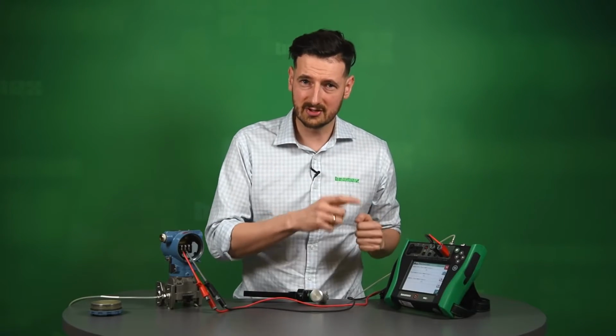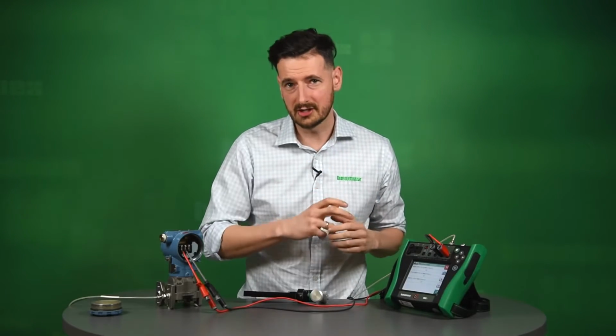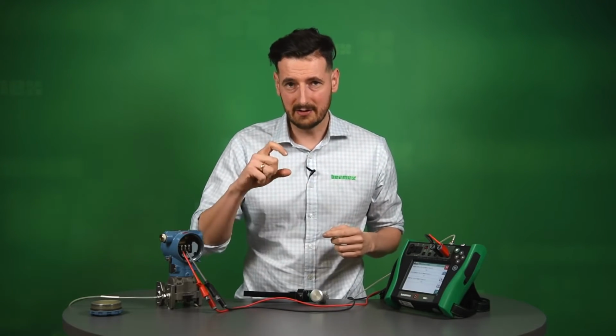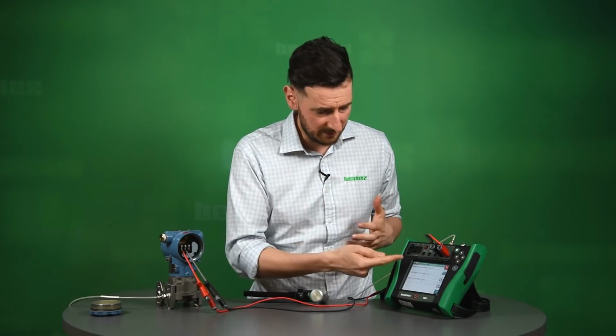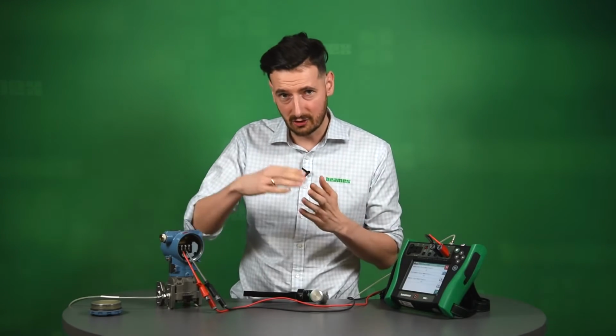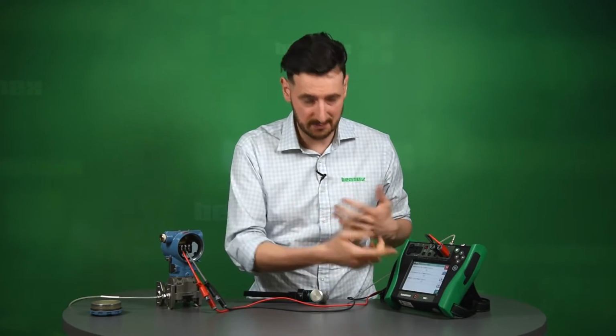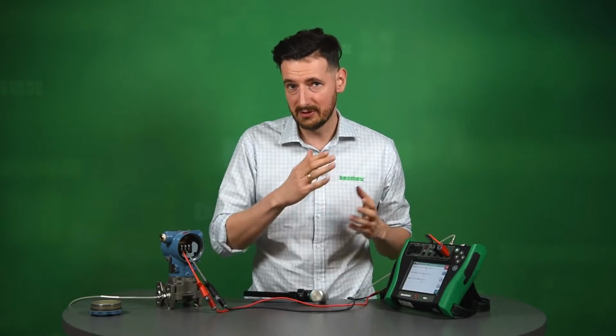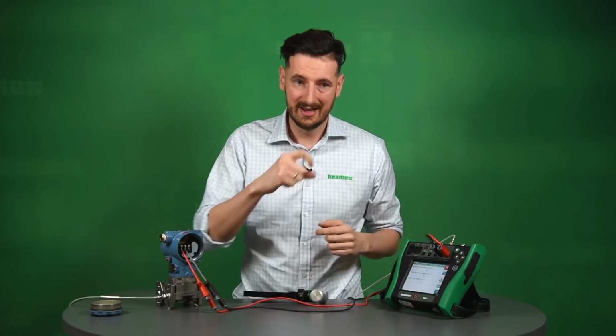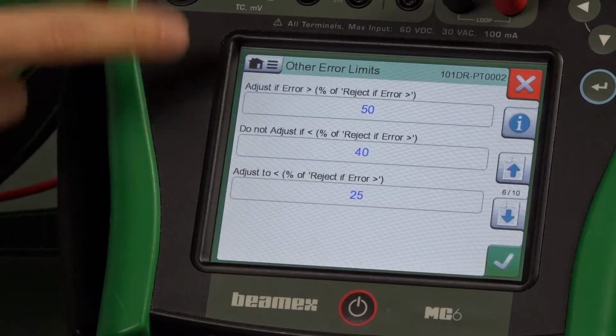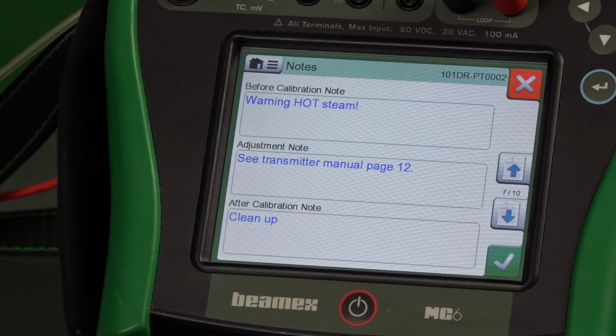Then we've also decided to give it additional conditions. These conditions are very practical. They are very often used in the sense that you can go up to a certain level of error. For instance, in this instance, 0.2 and above. If we go between 0.2 and 0.4, the calibrator is going to let us know that we should adjust according to our procedure. So this is our procedure. We're also going to have that.